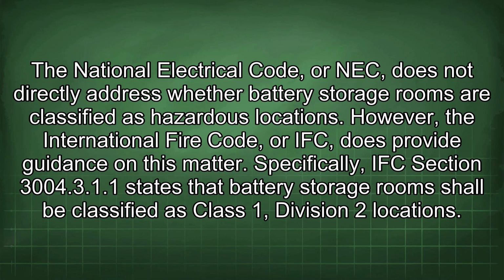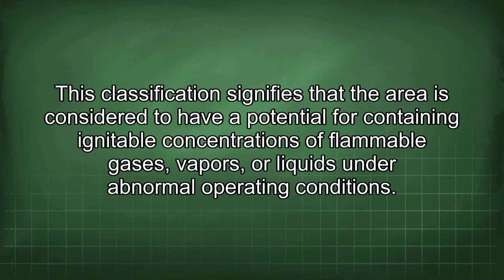The National Electrical Code, or NEC, does not directly address whether battery storage rooms are classified as hazardous locations. However, the International Fire Code, or IFC, does provide guidance on this matter. Specifically, IFC Section 3004.3.1.1 states that battery storage rooms shall be classified as Class 1, Division 2 locations. This classification signifies that the area is considered to have a potential for containing ignitable concentrations of flammable gases, vapors, or liquids under abnormal operating conditions.